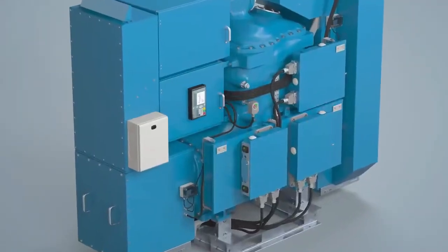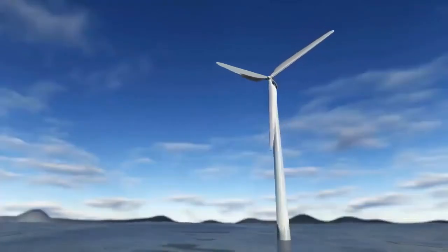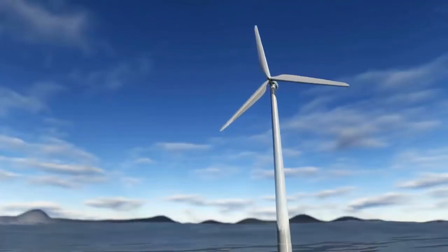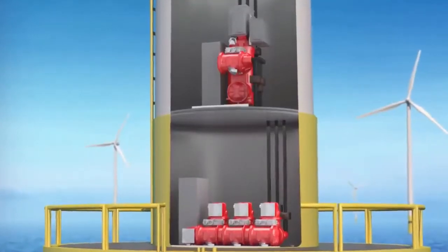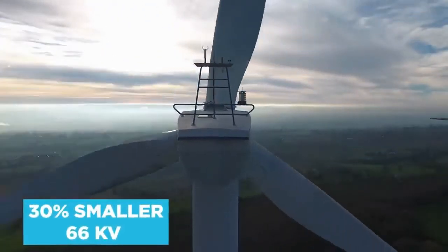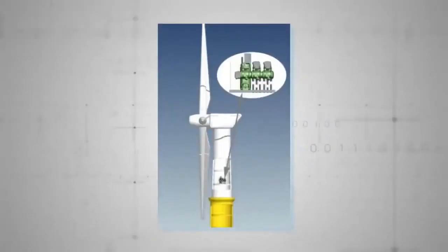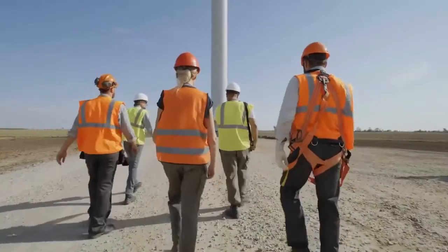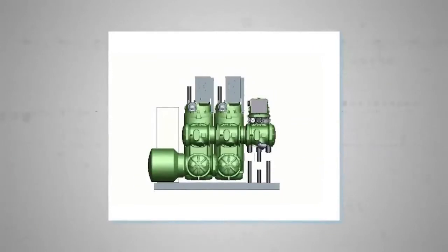At conventional onshore wind projects, these crucial switchgears occupy their own separate buildings connected to the turbines via cables. However, at sea that's not really an option, so engineers at GE set themselves the challenge of developing a switchgear powerful enough to function but small enough to fit into the tower. The result is the so-called F35, which at 2.4 meters high and 3.7 meters long is an impressive 30% smaller than previous 66kV switchgears. One solution mooted was to use a lower-voltage switchgear in the 33kV range, but that would mitigate the benefits of such a large turbine and mean less power would make it over to the land-based grid. As a happy offshoot of this project, the patented F35 switchgear can now be used on non-offshore and even non-wind-farm applications — it can fit under a city building, which is a great space saver for architects and planners.